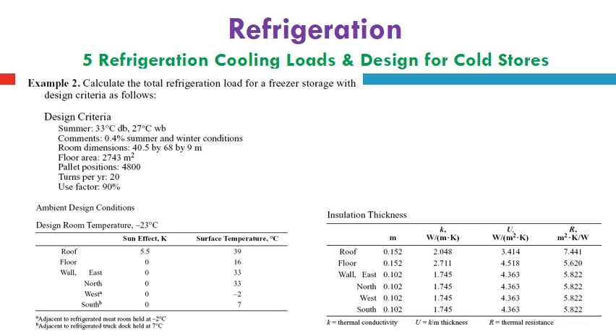The 0.4% summer and winter conditions can be taken from chapter 25, which was mentioned before. For the transmission load, the outside temperature is considered for major cities. Room dimensions are in meters: 40.5 by 68 by 9 meters in height, so the length, width and height of the room are listed. The floor area is estimated here as 2743 square meters.